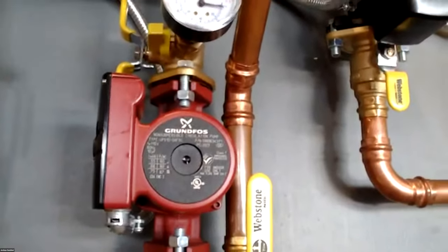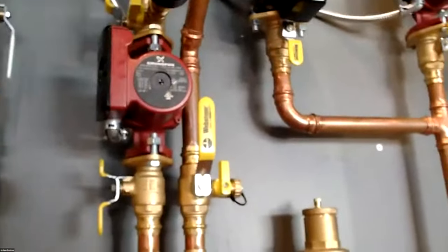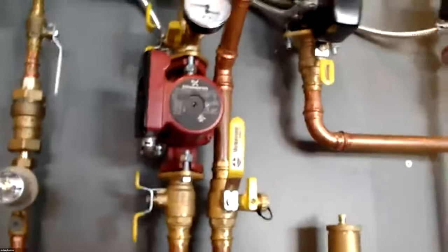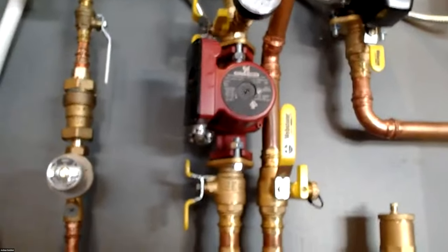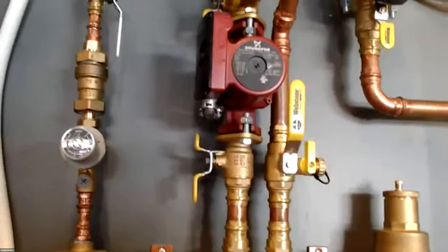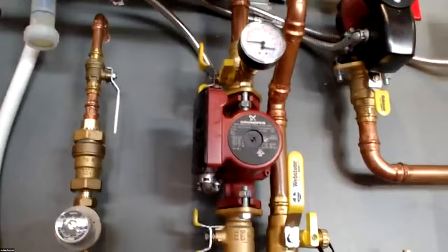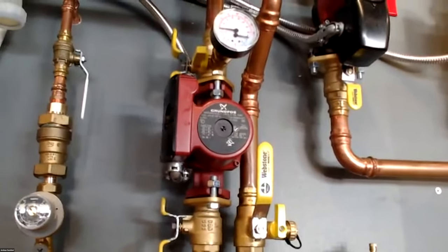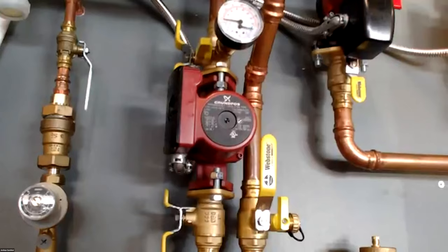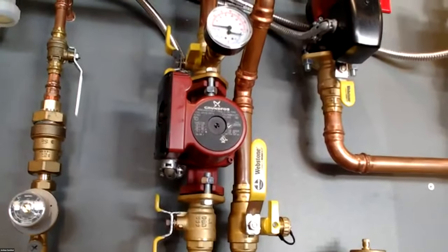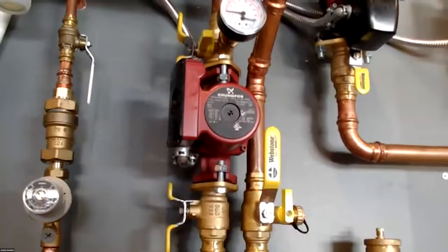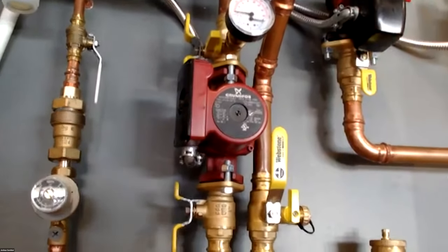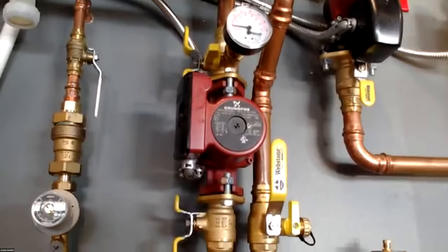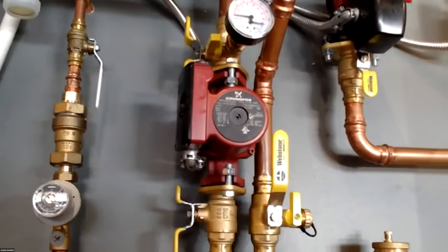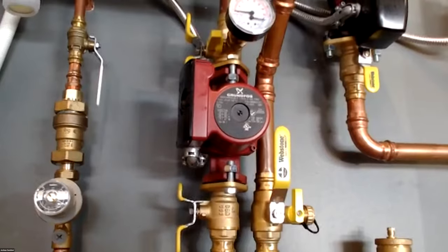Again, this one's pretty tight as well, but it shows this is a heat only, so we have our system pump, okay? Now, on the system pumps, combis have it. The boilers that are heat only, you would need to supply it. So these charts we'll go over. I'll pull up the PowerPoint, the manual, once we get done looking at these. I'll show you guys. But the 110, if you're using a Grundfos 15-58, totally good. That's totally fine. Taco 007 ECMs, though, no.